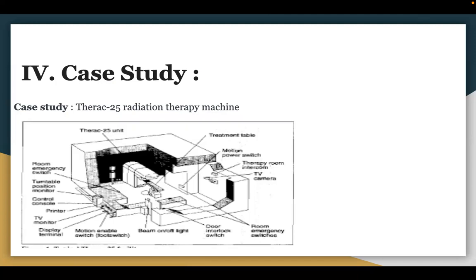The software was designed to control the amount of radiation delivered to patients. But a race condition in the code caused the machine to deliver massive overdoses of radiation in several cases, resulting in the death of some patients and serious injuries to others. The case highlights the importance of thorough testing and validation of medical device software, as well as the need for effective communication between software developers and medical professionals.